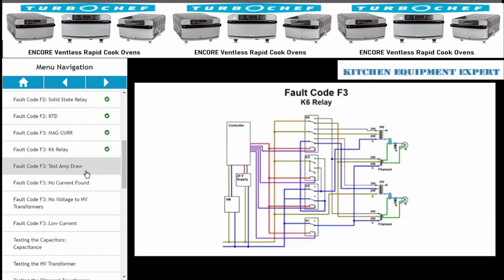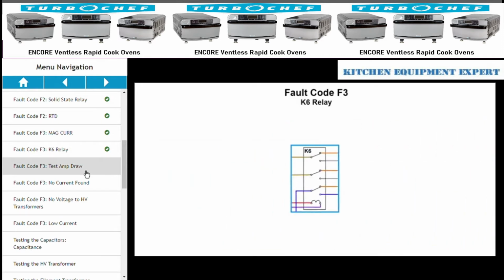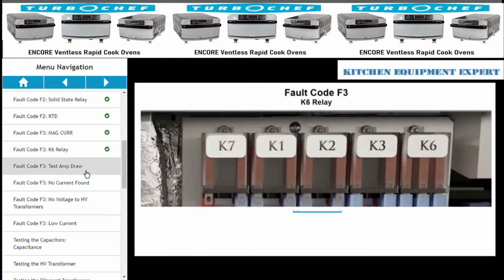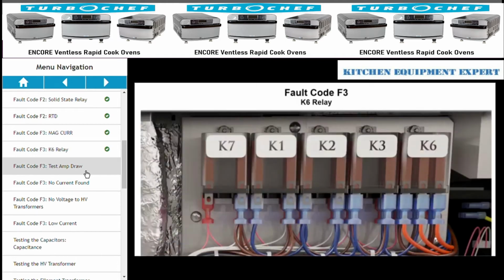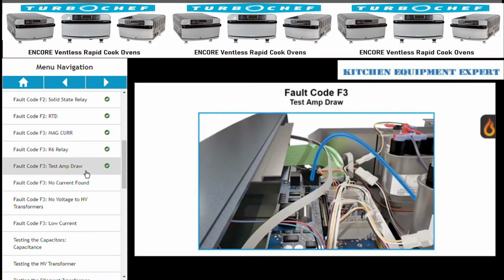In the case of a 208-volt unit, if it's not actuating, it could send 208 volts to the 240-volt primary windings of the transformers. This would result in a lower amp draw from the microwave circuits. Also, if the contacts inside the relay were bad, this could prevent one or the other of the microwave circuits from energizing. Make sure the K6 relay is functioning correctly. This brown wire carries the current for both microwave circuits.